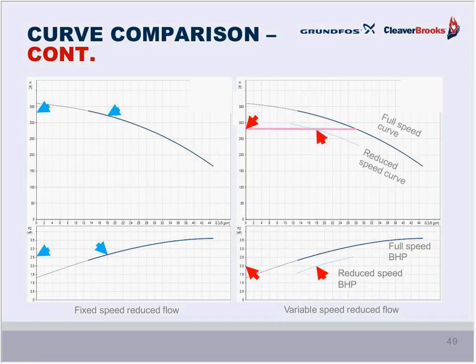So, as the variable speed pump modulates at reduced flow, there's also reduced head, and that adds up the power savings. And the lower the modulated flow, by the way, the greater the savings. So, you need a load profile on how your boiler will actually operate. And that's one of the major benefits of a variable speed pump.